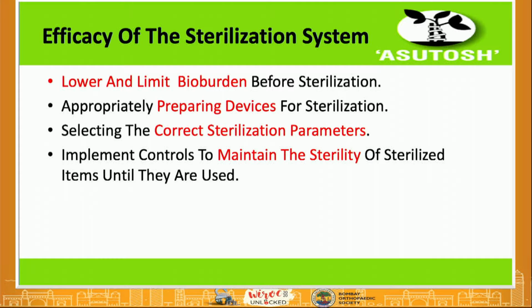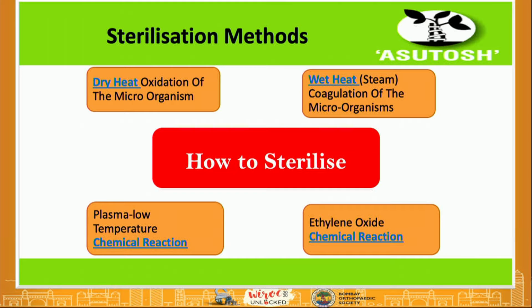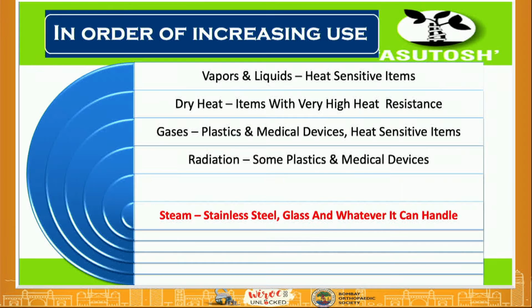But if you want an efficiency in your sterilization system, you have to lower and limit the bioburden. You have to adequately prepare the devices, have the correct sterilization parameters, and maintain the sterility even after the sterilization procedure has been done. The methods of sterilization are mainly the heat system, which is dry or wet heat, or the chemical systems, which is low temperature plasma or ethylene oxide.